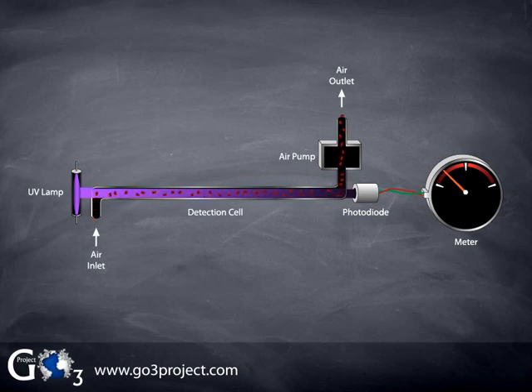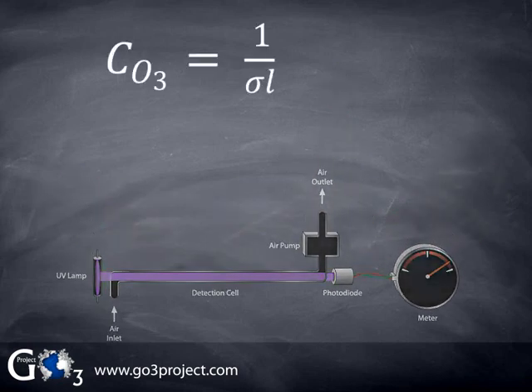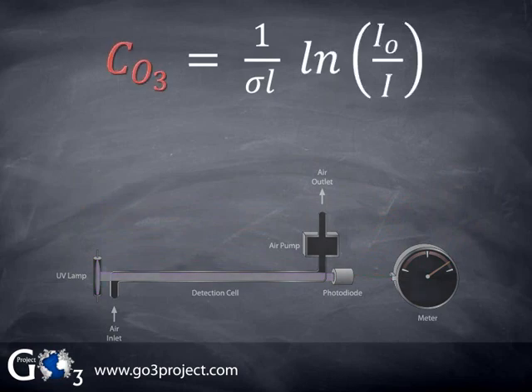If we stop passing ozone through the detection cell, the light intensity striking the photodiode goes up again and the meter reading increases. From our two light intensity measurements, measurements with and without ozone molecules present, we can calculate the ozone concentration based on the Beer-Lambert law for absorbance of light.